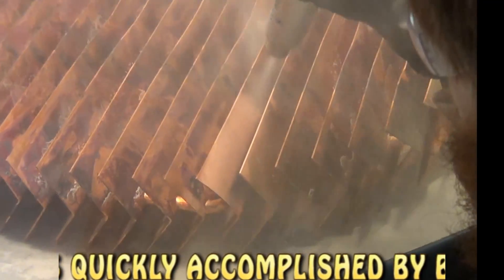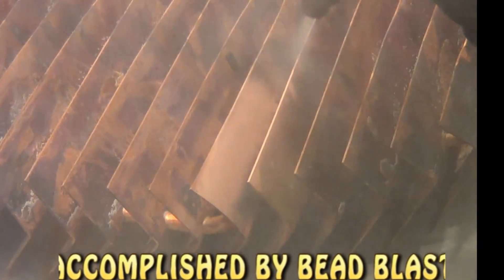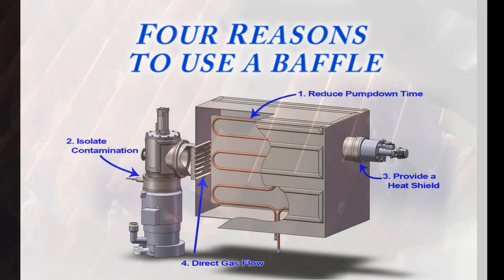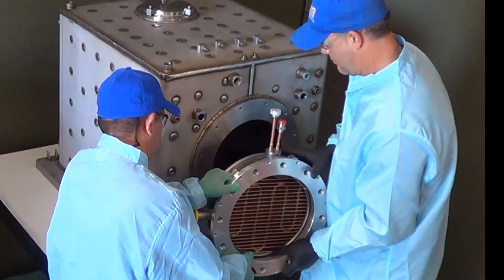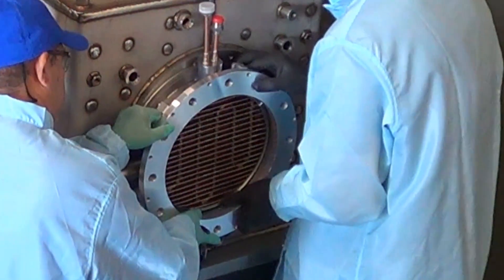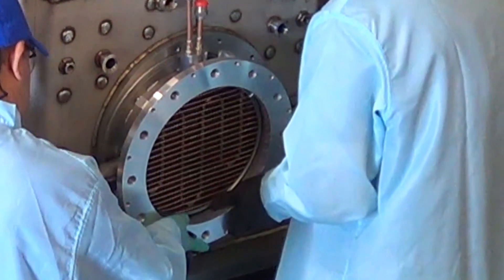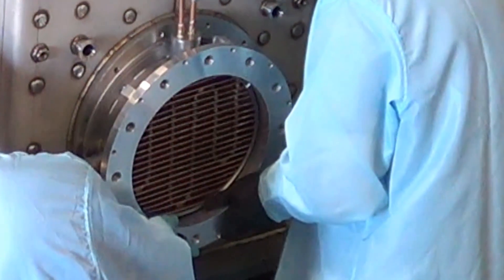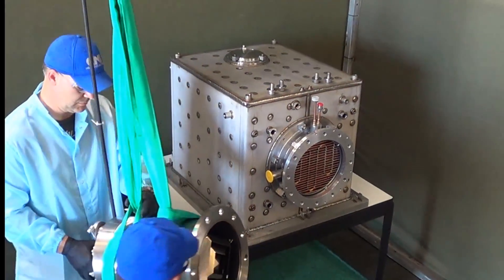The third common use of a baffle is to provide a heat shield. Many vacuum components such as cryo pumps do not work effectively when exposed to the high temperatures commonly found in vacuum processes. A chilled baffle placed in front of a cryo pump will block radiation and allow the pump to work efficiently.